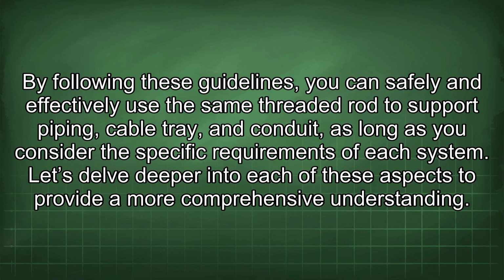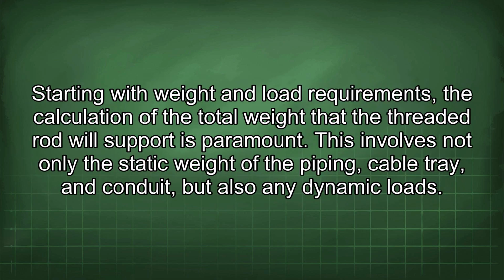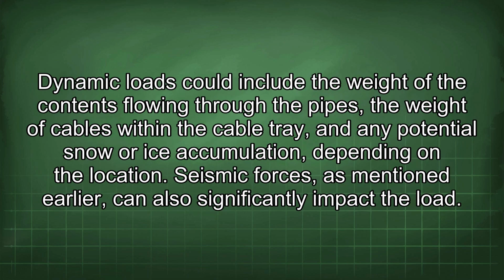Let's delve deeper into each of these aspects to provide a more comprehensive understanding. Starting with weight and load requirements, the calculation of the total weight that the threaded rod will support is paramount. This involves not only the static weight of the piping, cable tray, and conduit, but also any dynamic loads. Dynamic loads could include the weight of the contents flowing through the pipes, the weight of cables within the cable tray, and any potential snow or ice accumulation, depending on the location. Seismic forces, as mentioned earlier, can also significantly impact the load.